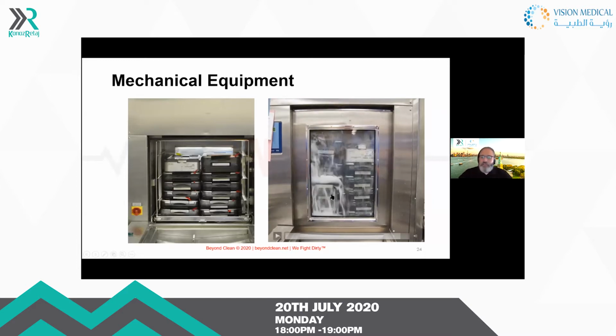So I hope you all can see here that this washer disinfector is not functioning the way that it should be working. We have a song here in the United States where the group says, "Don't go chasing waterfalls." And I think that was a perfect illustration of a waterfall on the left side of that washer disinfector. But as you know, most washer disinfectors will hold 6 full-size trays. In this picture on the left, this hospital had 12 trays in their facility with the lids still on them, and they also placed locks so the lids could not come off.